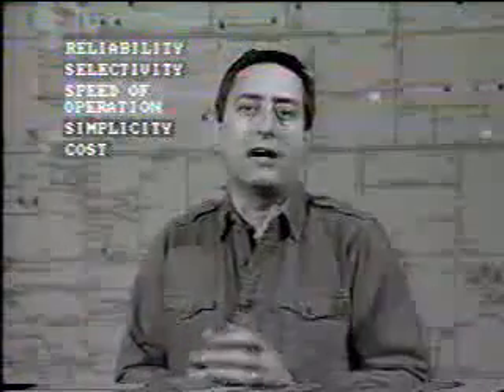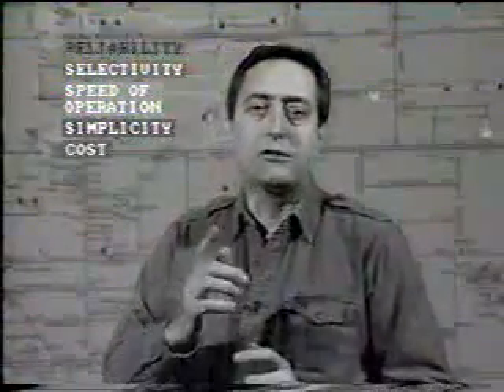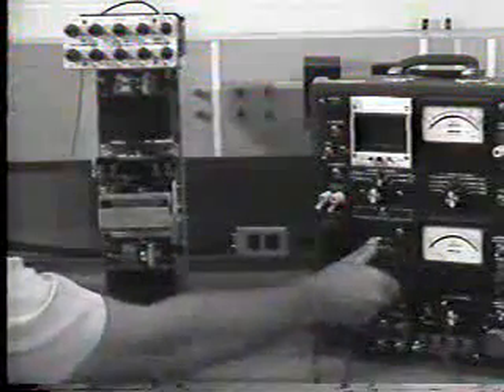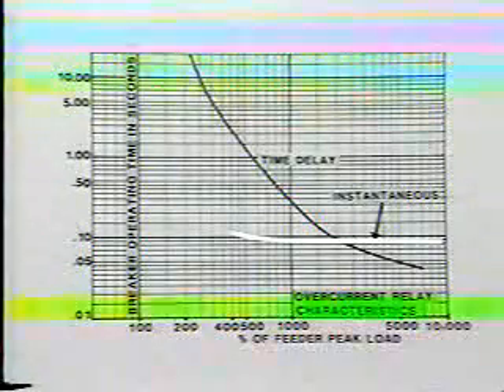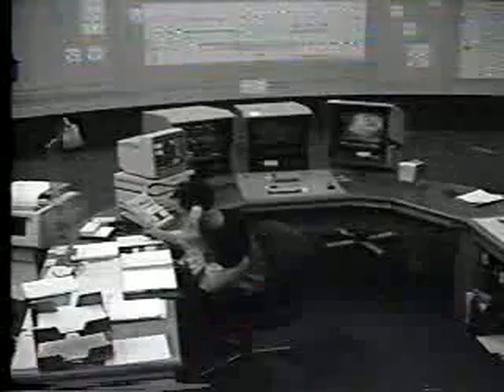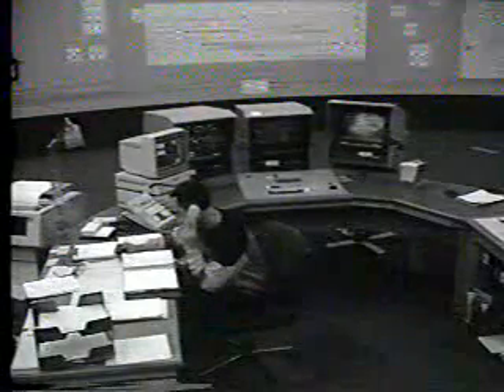To summarize now, we can say that there are five basic factors in application of protective relays. And these are: 1, reliability; 2, selectivity; 3, speed of operation; 4, simplicity; and 5, cost. The last two items speak for themselves, but let's look a little closer at the others. First, we have to rely upon the relay or relay system operating correctly, that is, to operate and trip out the faulty circuit when it's necessary to do so. The reliability of the relay is tested by inputting current and voltage which simulate fault conditions. The time of operation can be measured in relation to the degree of fault condition. A second aspect of reliability is that the system must not trip out during normal operation.